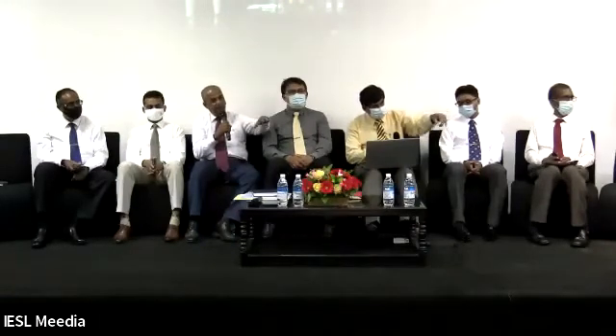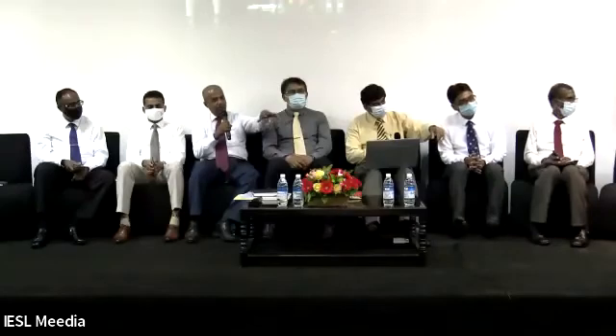Okay, somebody said there was a fire lit under the tower, somebody had interviewed an old woman who said it was done. But we were not concerned about that. We just accepted that there had been some fault which triggered differential protection on phase B of line 2. There is no issue there. But what happened after that is the real problem, right? Why did end-fault protection activate? Because if line protection has operated, end-fault protection should have been inhibited. It cannot operate in theory, right?